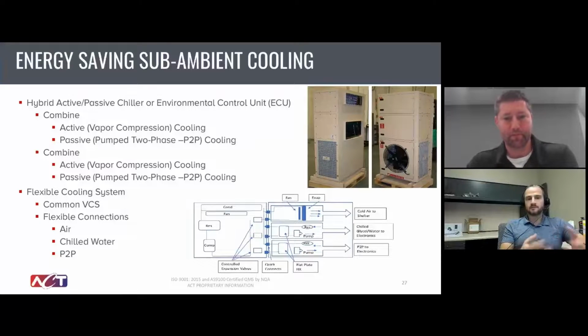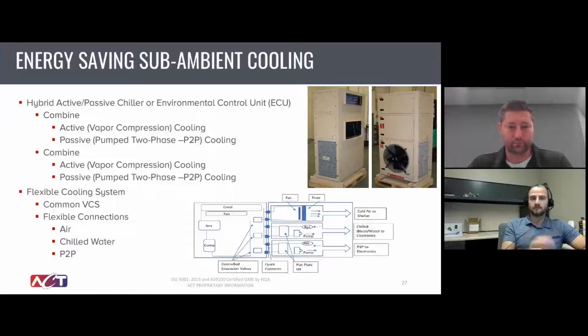The reason you would do this is for applications where you can't just open the window. Another way to do this would be to turn off the air conditioner and just open a window essentially, or open up a louver. There are a lot of applications where the environment's dirty, dusty, toxic, or corrosive. Lots of reasons you wouldn't want that outside air inside of your system. This is where this solution really shines. So you get the eco mode, the energy savings of the outside air when the ambient is sufficient, and the subambient cooling for those hotter days of the year, all within one nicely packaged system.